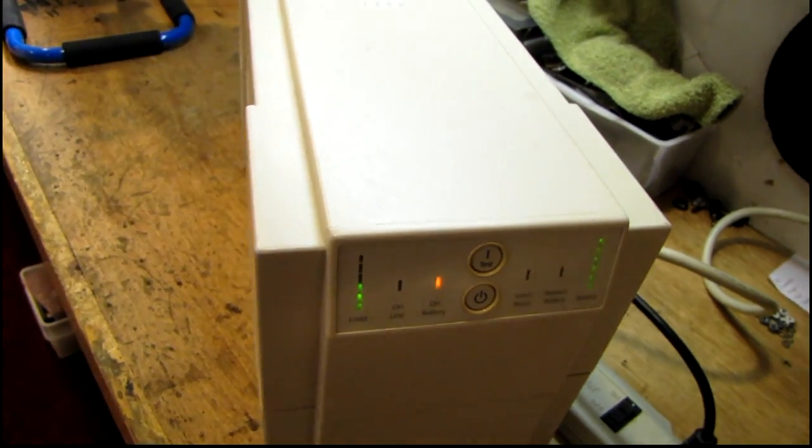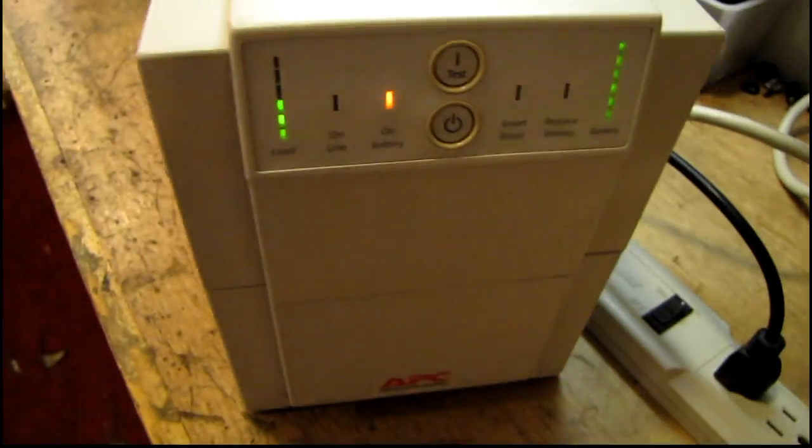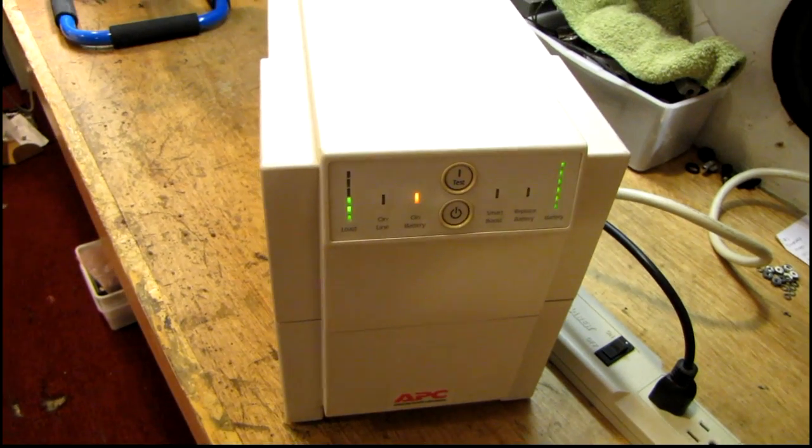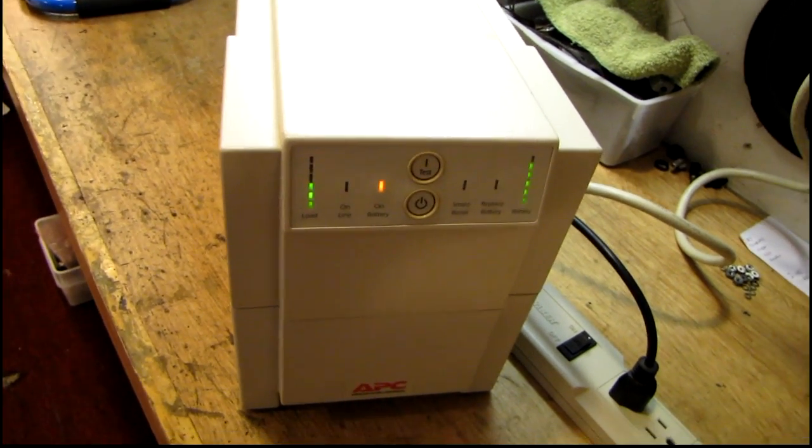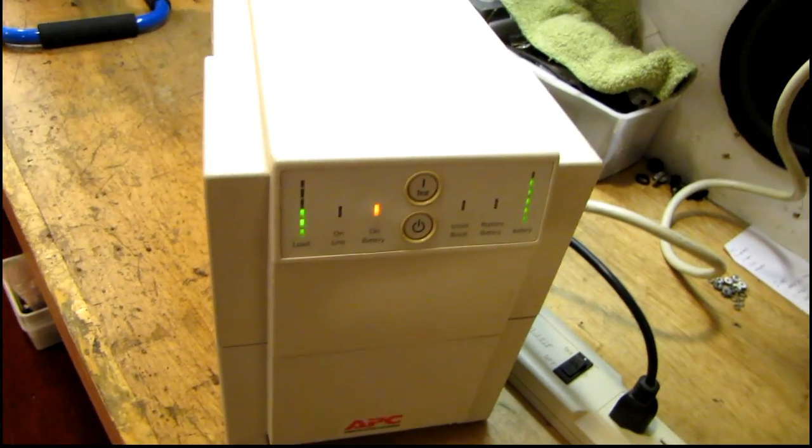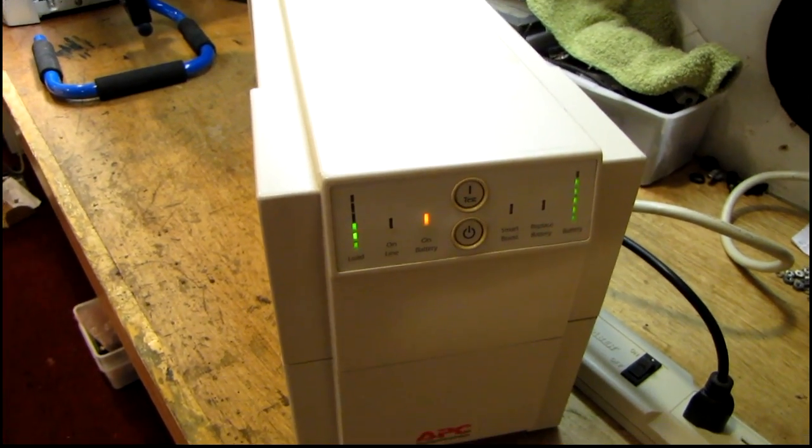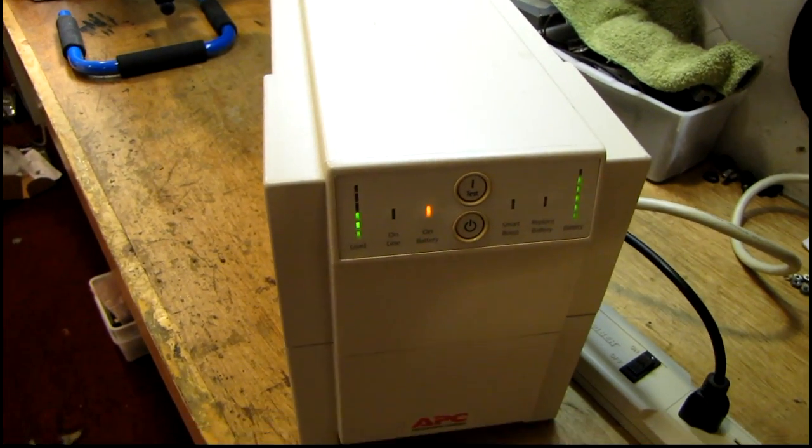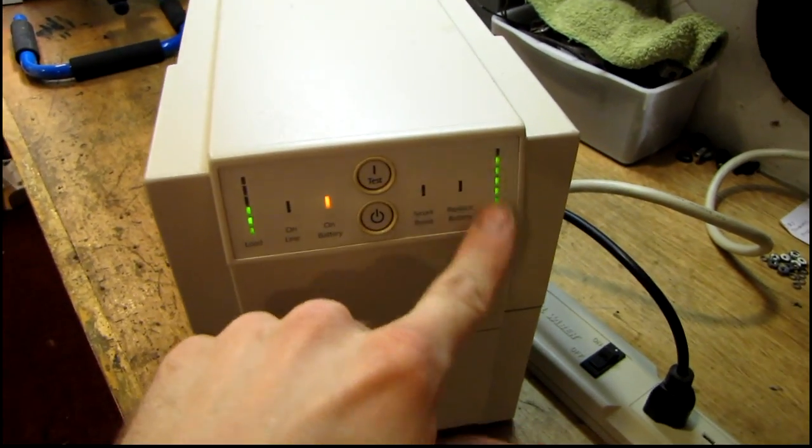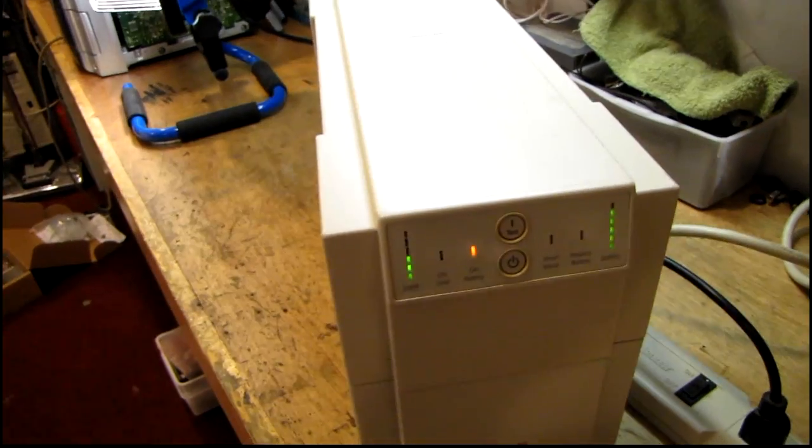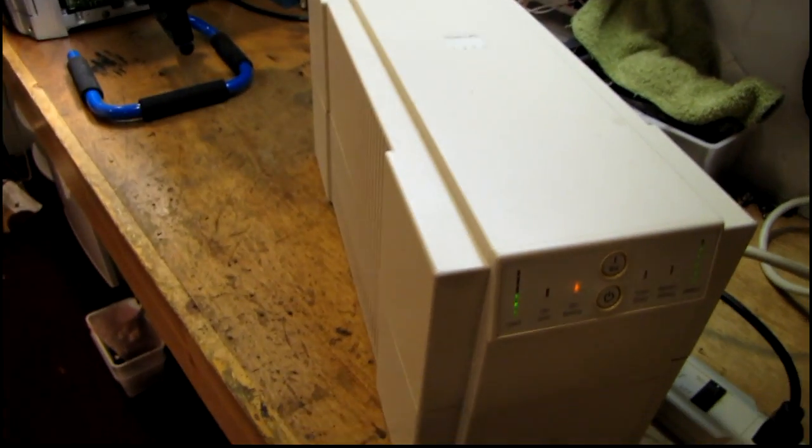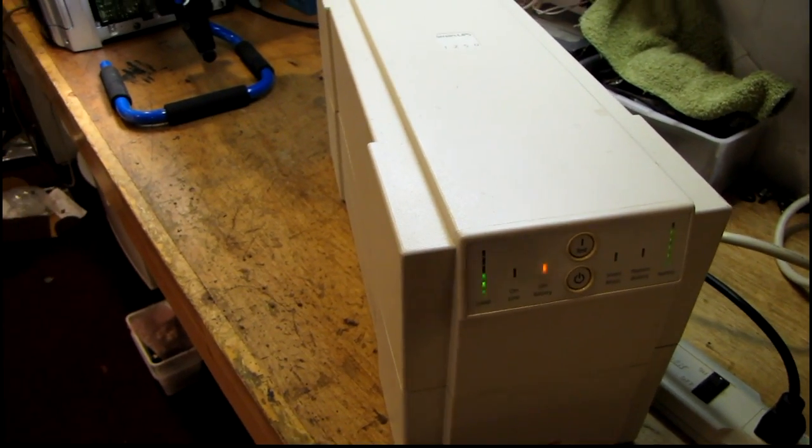Now, this is the annoying part. You need to let the unit run on battery power until it goes completely dead and shuts off on its own. At that point, you can remove the load, turn the UPS back on, let it fully charge, and then it's ready for use. And the battery gauge will be totally accurate at that time, too. So I don't know how long this is going to take. Probably about 45 minutes.